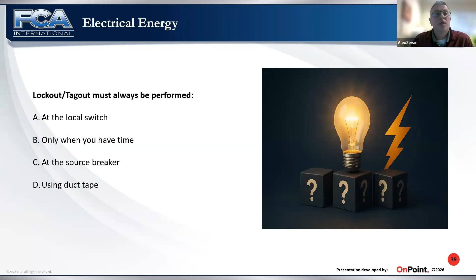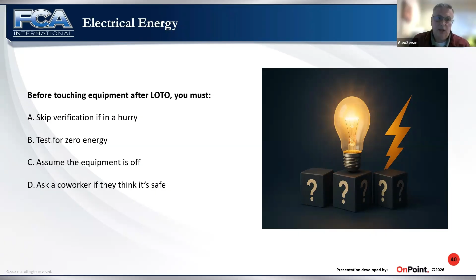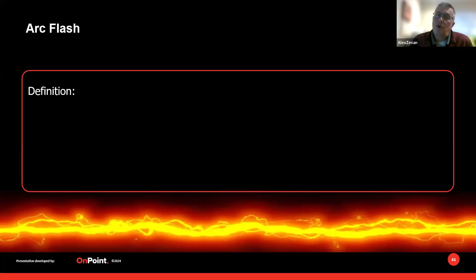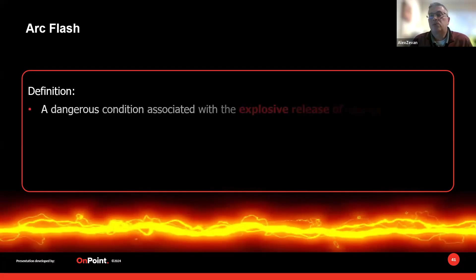Lockout tagout must always be performed at the source breaker. Always make sure you go back to the source where the energy is coming from. And before touching equipment, after lockout tagout, you must test for zero energy. Always make sure that it is not alive before you do your work. So here's your arc flash, and this is what we're moving towards at the end of our presentation, but arc flash does need to be explained. Arc flash is the explosive release of energy caused by an electrical arc, either phase to phase or phase to ground. So this temperature can be very, very hot. As you can see, temperatures can rise well into the 35,000 Fahrenheit.